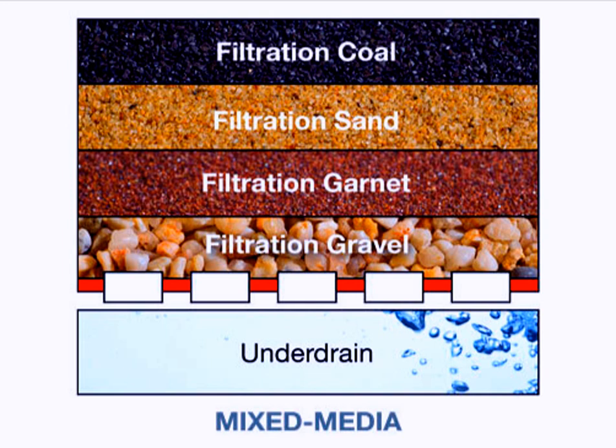The total gravel bed may be from 6 to 18 inches, that is 150 to 450 millimeters thick, depending on the type of under-drain system. Many types of filter under-drain systems are now available that do not require a gravel layer.